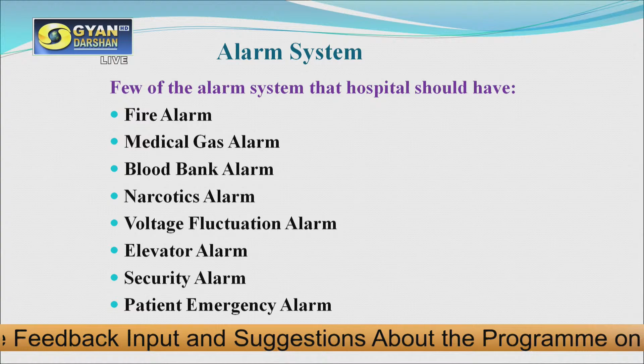Now when the electric power supply goes and the generator comes on, there is a lag period, so the temperature will dip. If that happens repetitively, then when the inspecting authority comes to inspect after 2 or 3 years, there will be a problem. Elevator alarm system, security and patient emergency. The same kind of mechanism may also be utilized for vaccinations. Cold storage.